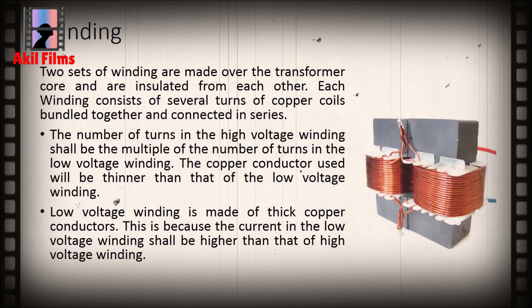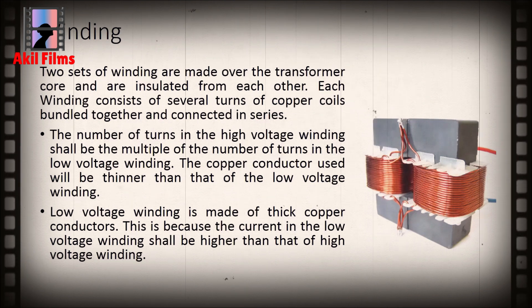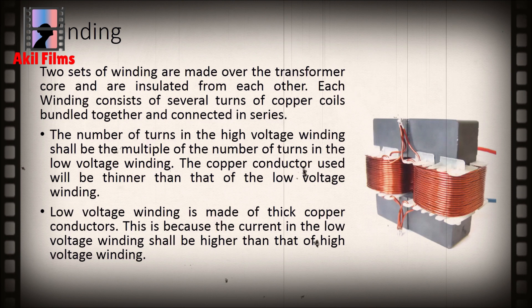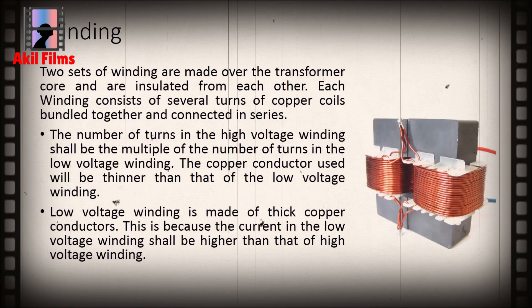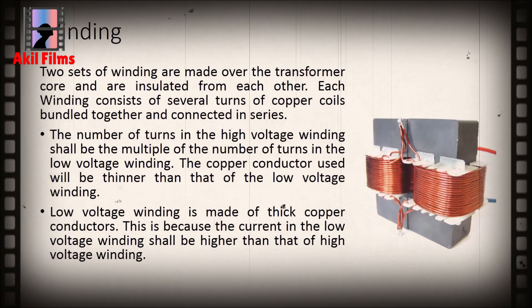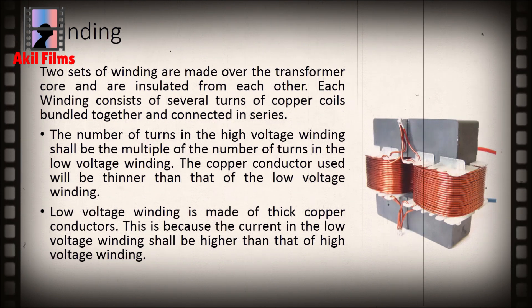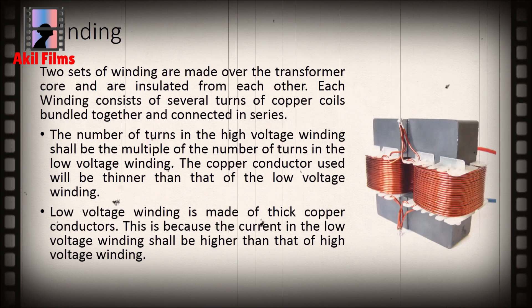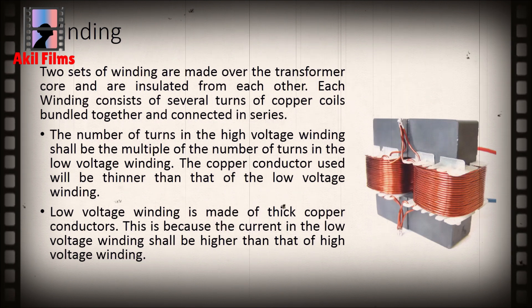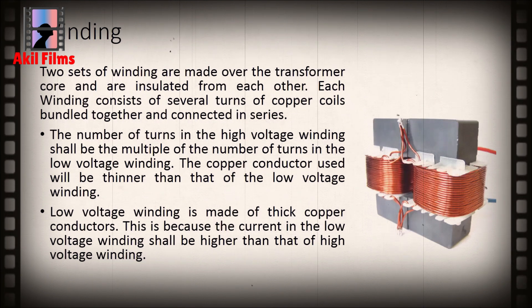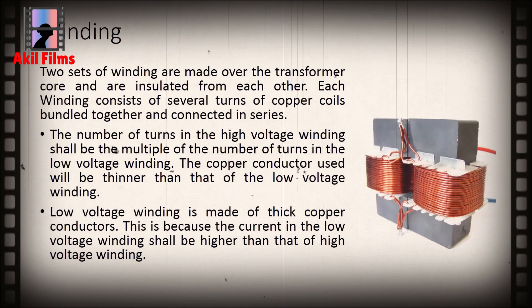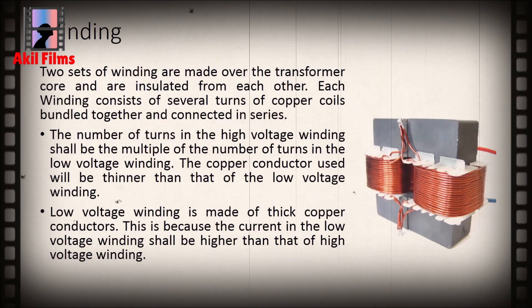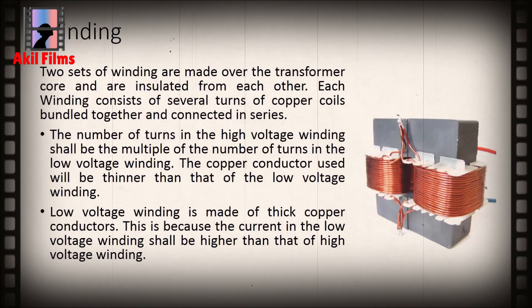Each winding consists of several turns of copper coils bundled together and connected in series. The number of turns in the high voltage winding shall be a multiple of the number of turns in the low voltage winding. The copper conductor used in the high voltage winding will be thinner than those of the low voltage winding.